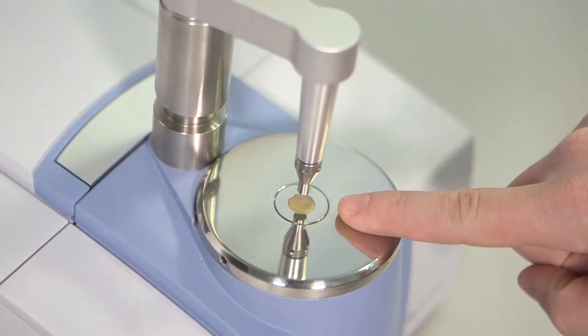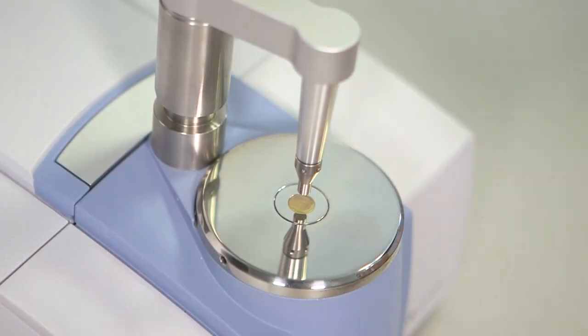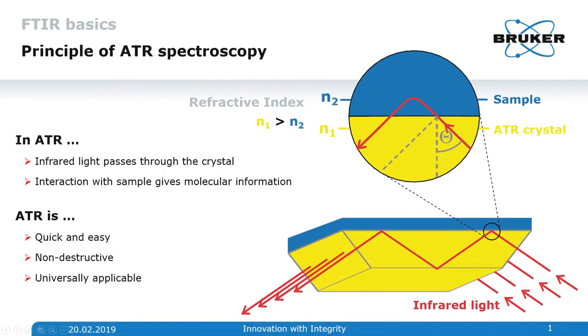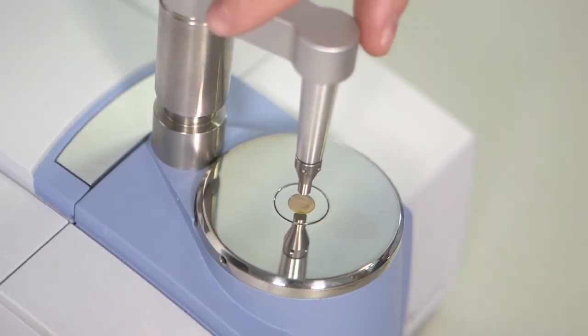This yellow zinc selenide crystal is where the measurement takes place. Infrared light passes through the crystal and interacts with the material on top, providing molecular information. This method is fast and easy, non-destructive, and universally applicable.